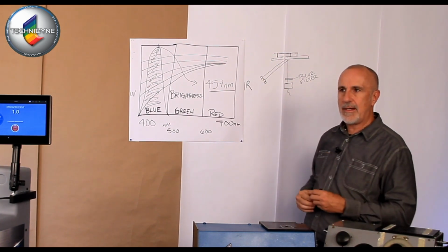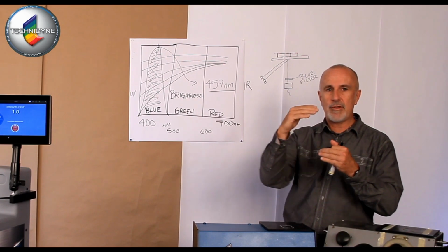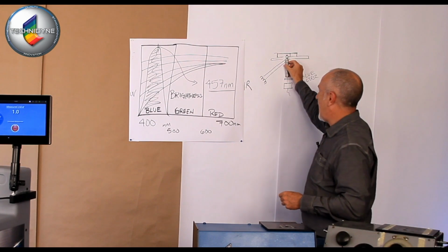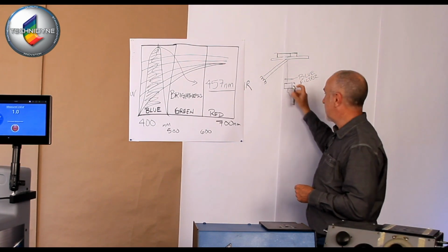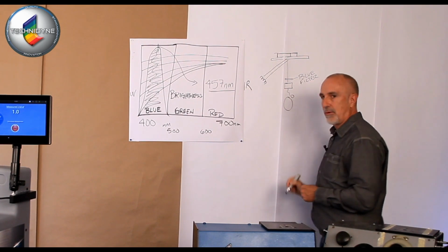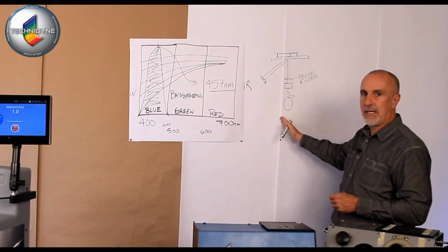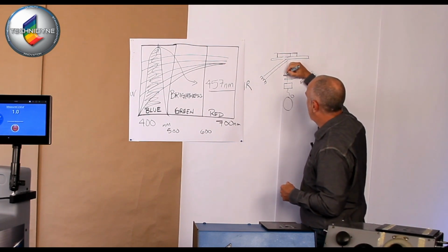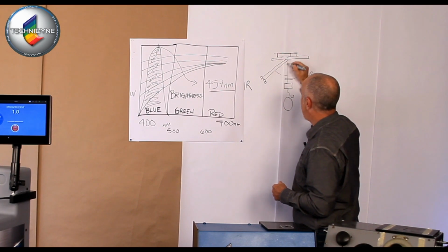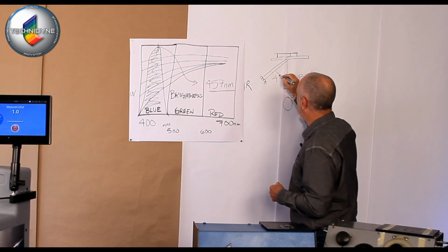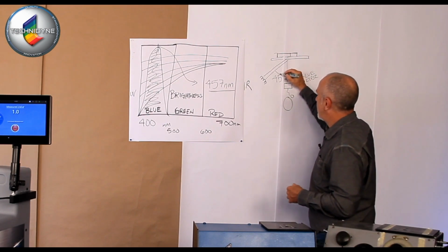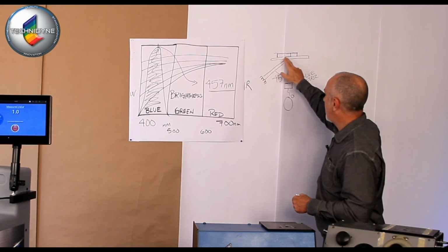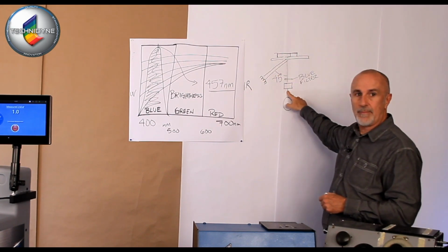And whenever you're talking about instrument geometries, okay, we always reference the sample's perpendicular. So if the sample sets here, the perpendicular axis of that is where the photocell sets, and that's defined as 0 degrees, okay? So you have 0 degree viewing on this instrument. And then you would come off, you'd rotate off this, and you'd define this angle here. And for the TAPPI method, or what was originally developed by General Electric, that was 45 degrees. Okay, so now you have 45 degree illumination and 0 degree viewing.